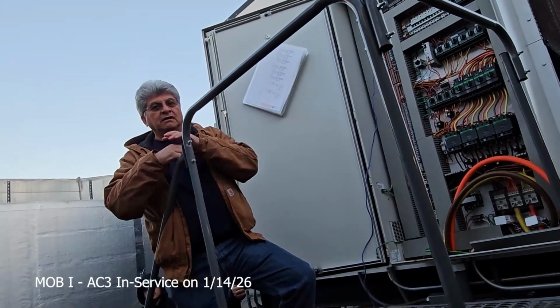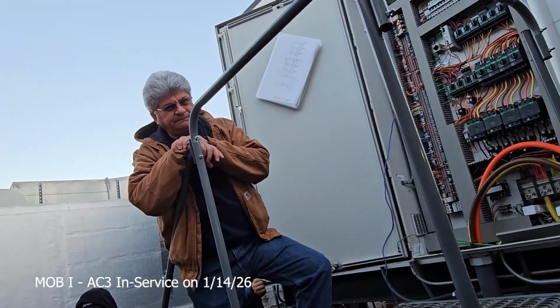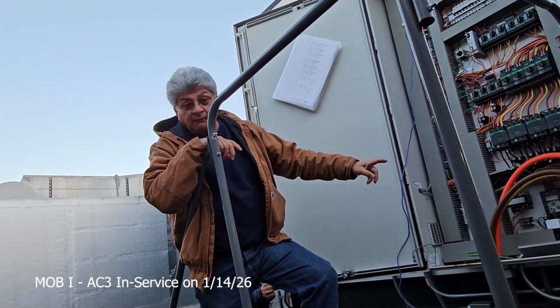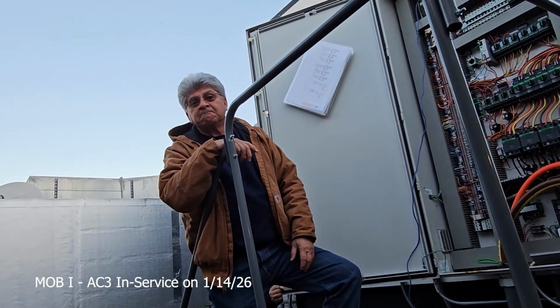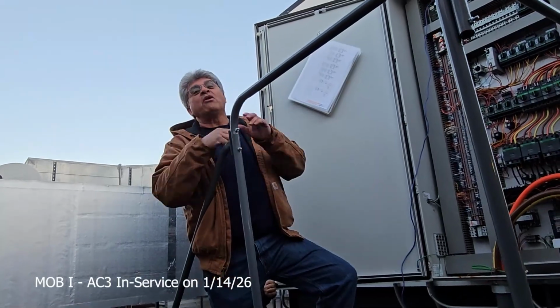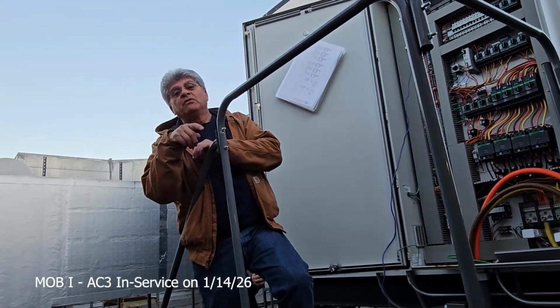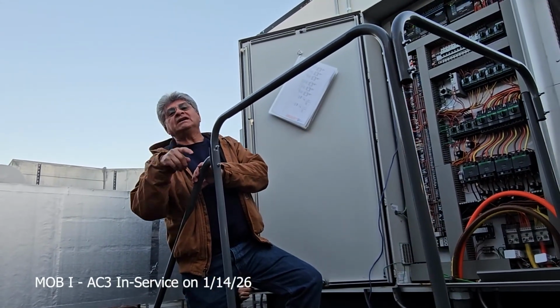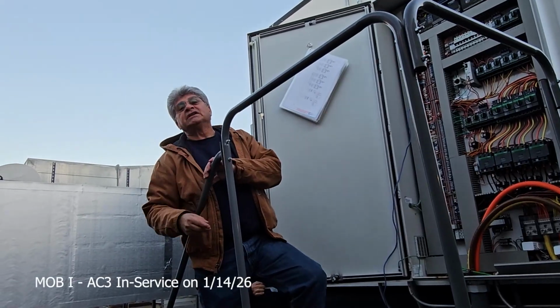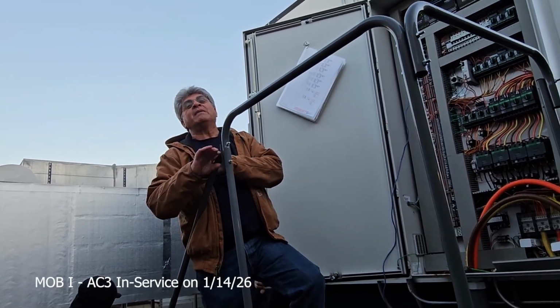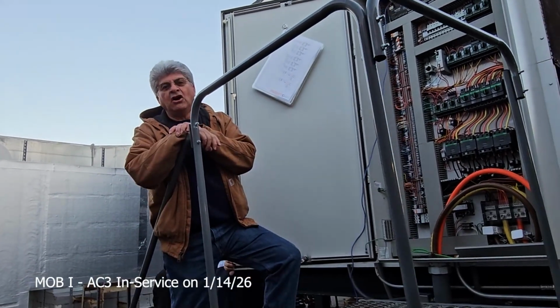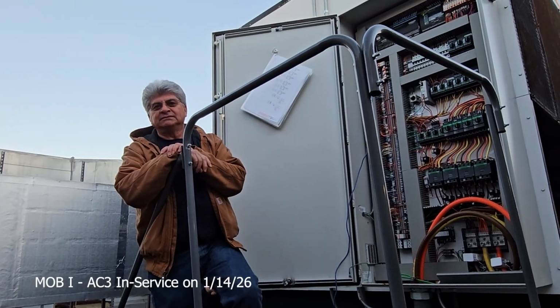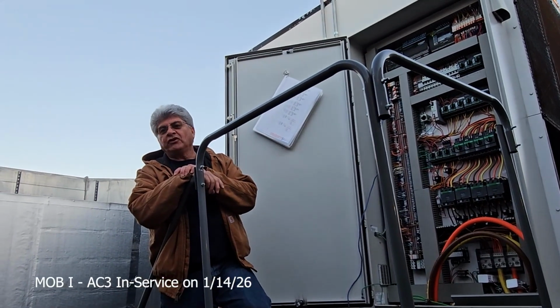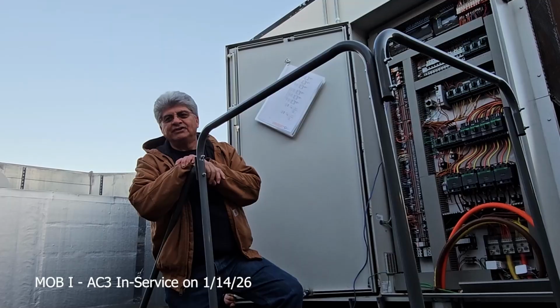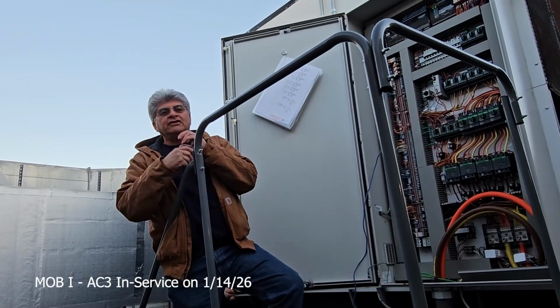So you're saying that if I have a red, black, and I can switch over, and the motors run fine? The motor will still run clockwise if it was programmed to run clockwise. Switch any 2 legs you like, it should still run clockwise no matter what. Okay. All right. Only ECM motors do that. All your other Baldor motors, you change rotation by changing your phase leg.